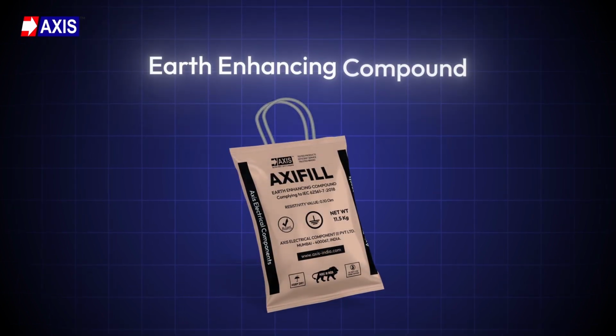Salt, when mixed with water, is ionized and becomes corrosive to the earth electrodes. It also requires constant maintenance and watering. Charcoal degrades over time and loses its ability to hold moisture. Both materials are not maintenance-free and will corrode your earth rod in the long run. Therefore, earth-enhancing compounds are preferred.